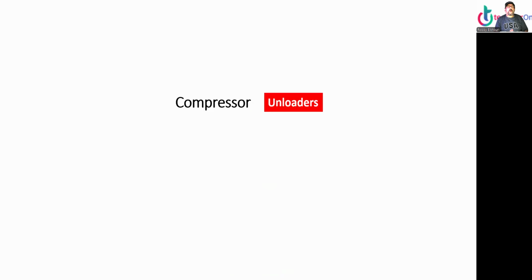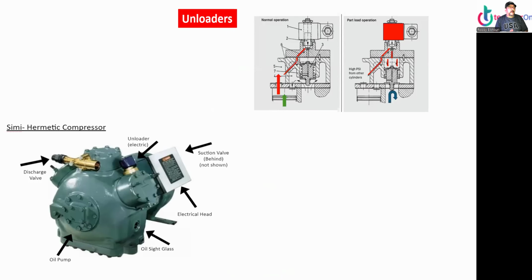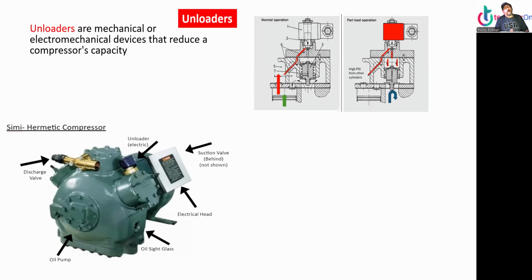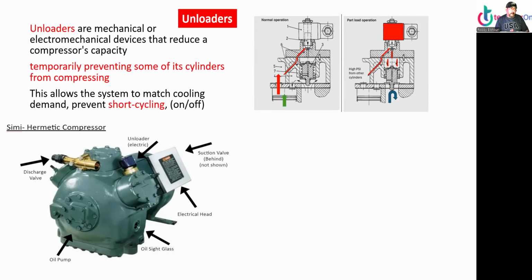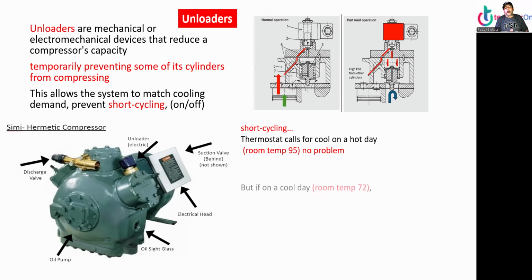Now, let's talk about unloaders. Compressor unloaders go on from the outside, they unload the head. Unloaders are mechanical or electromechanical devices that reduce the compressor's capacity, temporarily preventing some of its cylinders from compressing. This allows the system to match cooling demand and prevents short cycling on and off. Short cycling, thermostat calls for cool. This is the example. Thermostat calls for cool on a hot day. Room temperature 95, no problem.